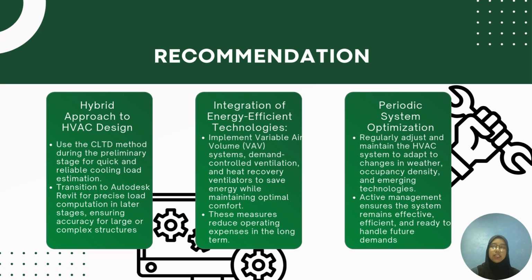Okay, next for the recommendation to enhance the efficiency and reliability of the HVAC design, we propose a hybrid approach. The CLTD method should be used in the preliminary stage for quick and reliable estimation, followed by precise load computation using Autodesk Revit in the later stage. Additionally, integrating energy efficient technology like variable air volume system, demand control ventilation, and heat recovery ventilator can significantly reduce operating costs while maintaining comfort.